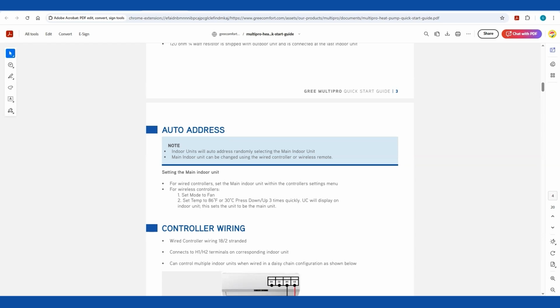That's very important that you talk with the homeowner and make sure they understand the master controls the mode. So if the master is in heat mode, the rest of the units can only work in heat mode. If the master or the main indoor unit is in cooling, then all of the indoor units can only be in cooling. Keep that in mind. Make sure you explain that to the homeowner.